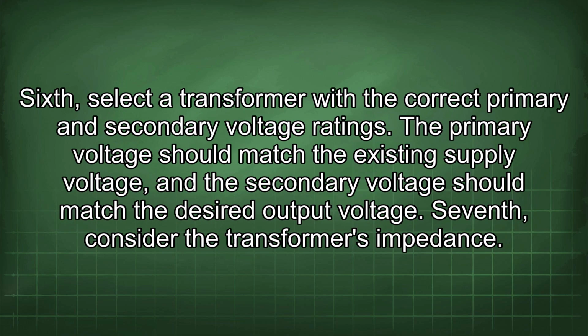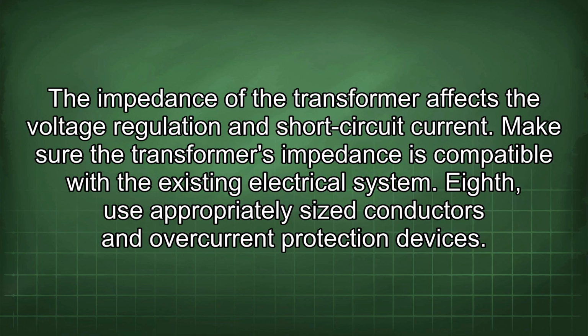Sixth, select a transformer with the correct primary and secondary voltage ratings. The primary voltage should match the existing supply voltage, and the secondary voltage should match the desired output voltage. Seventh, consider the transformer's impedance. The impedance of the transformer affects the voltage regulation and short-circuit current. Make sure the transformer's impedance is compatible with the existing electrical system.